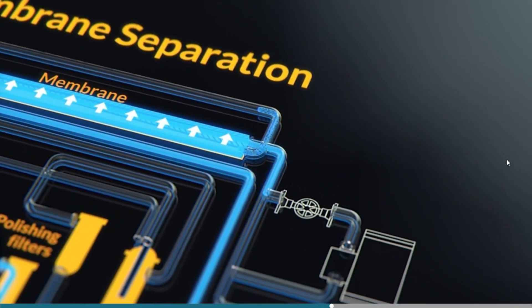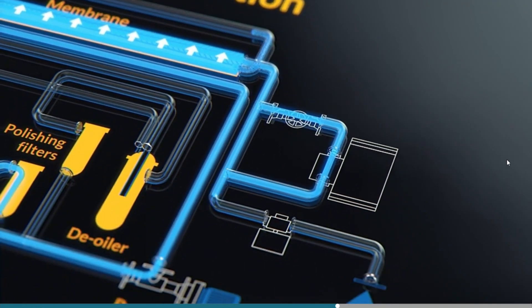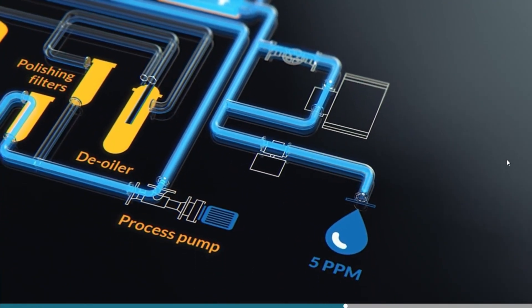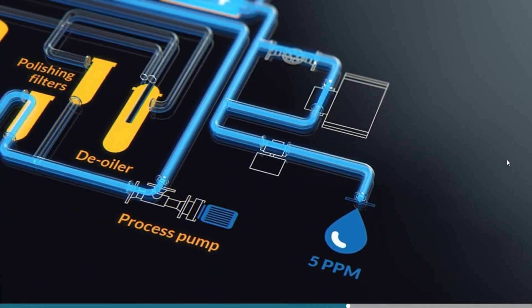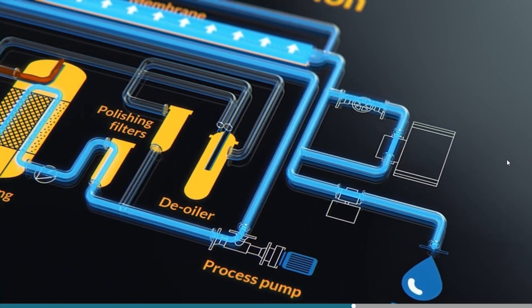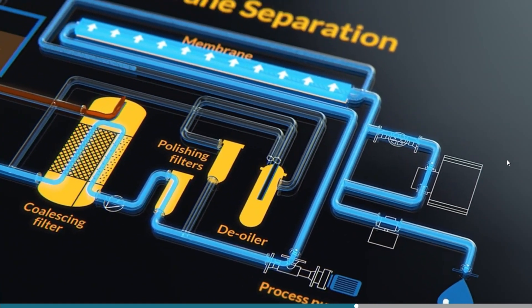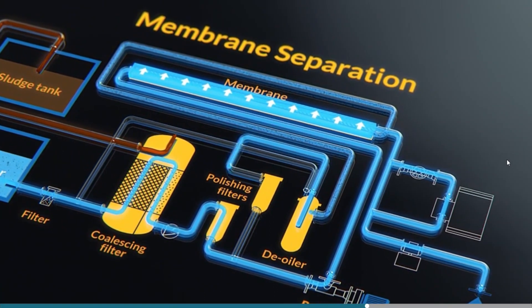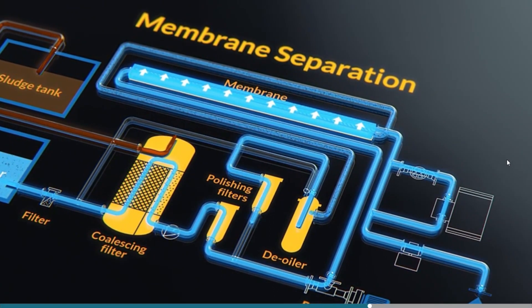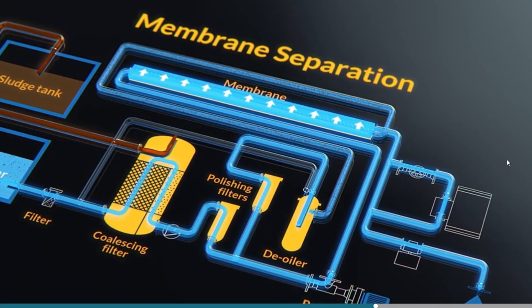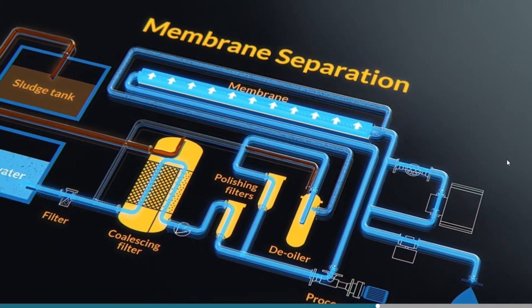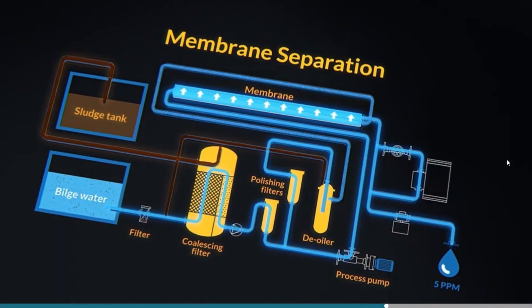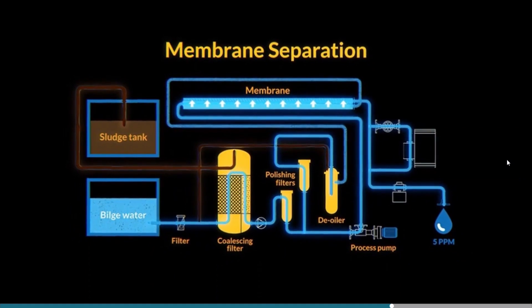The clean water passes through the oil monitoring equipment and overboard. The rejected water is directed back to a de-oiler reservoir, which removes the oil and sends the water through a filter and back to the process pump. The oil is sent back to the inlet side of the oily water separator, from where it will be discharged to the sludge tank.